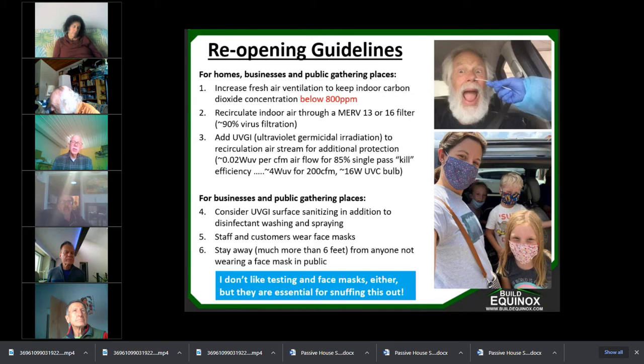There's an excellent webinar by Bill Bonfleth, a professor at Penn State University and former ASHRAE president, but also a world-renowned expert in UVGI. His webinar is available free online, but basically at about 4 watts of electric power per person, or about 16 watts of electric UVC bulb, which is about 4 watts of UV power, and for about 200 CFM of airflow rate, that will give you about an 85% kill efficiency of a virus.